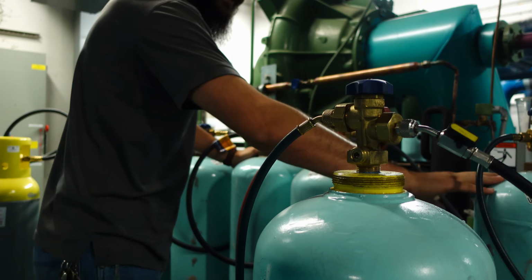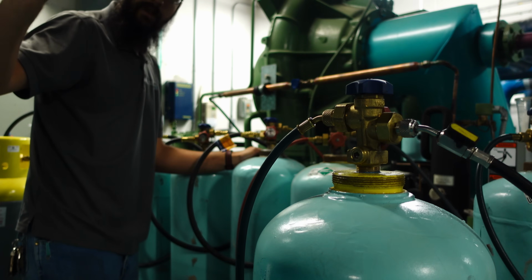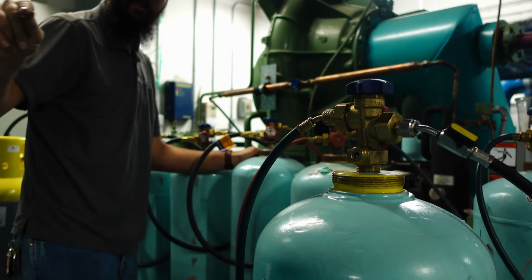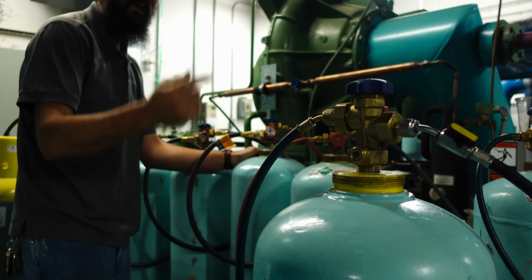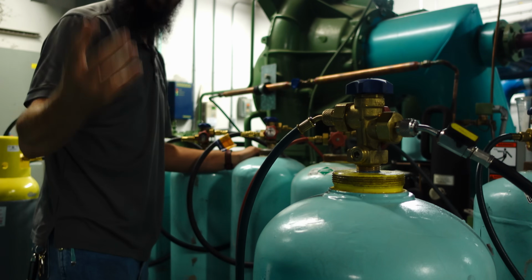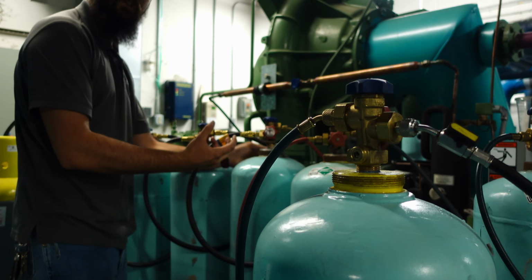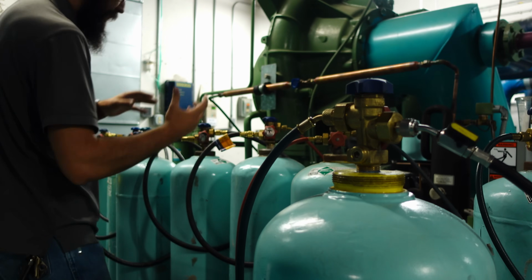The discharge gases, since I'm doing push-pull, means I'm not going through the subcooler on this recovery machine, which helps here because I want that extra heat to push into these tanks, since that's going to help get that refrigerant to move.